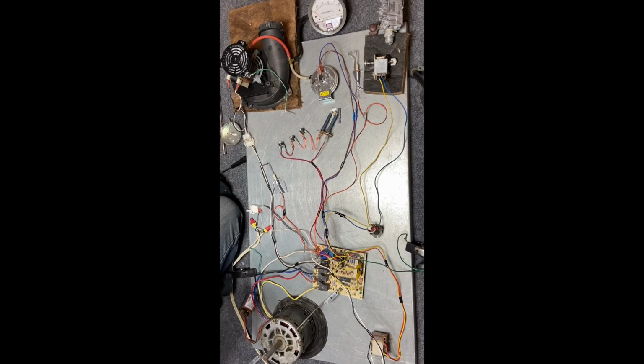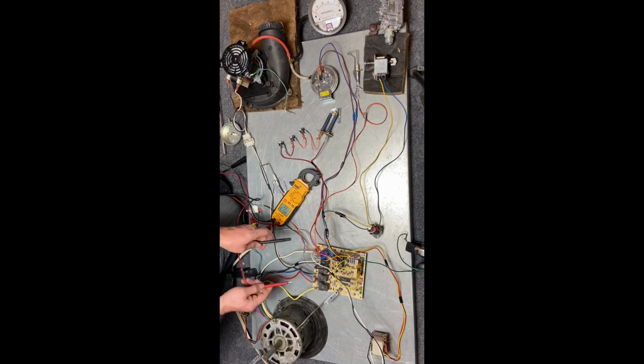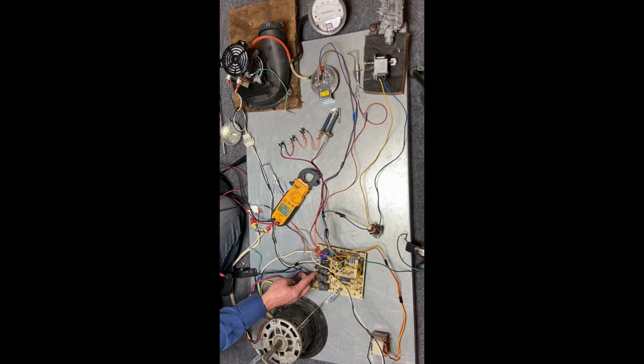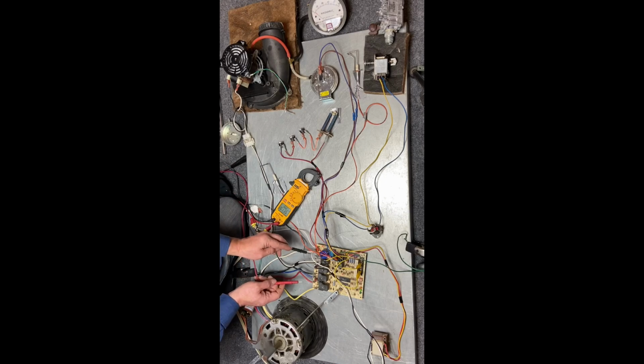Now one thing I want to note is when you're checking multiple speeds of the motor and you check voltage between neutral and any of these terminals, you're going to read voltage between all the terminals because the electricity is backfeeding through the motor to the other components, which is why we can only energize one speed at a time. I'm energizing high speed right now. Then we'll disconnect and connect here, or disconnect and connect here. We can only run one speed at a time through one of these legs and back home. So if I check voltage, because of that backfeed, we're going to show voltage on all of these.